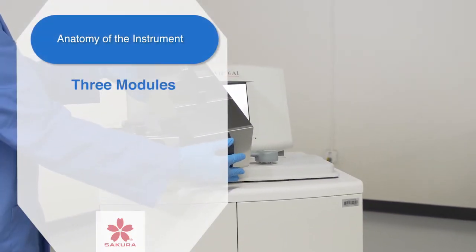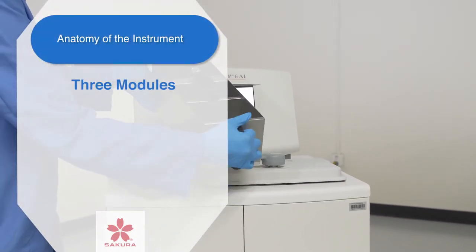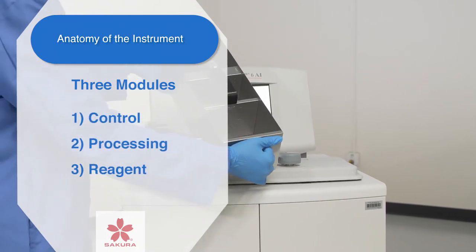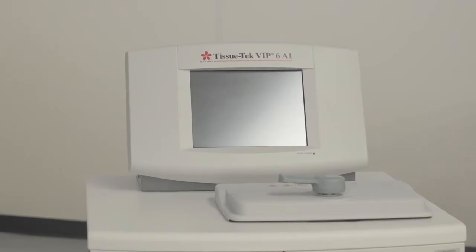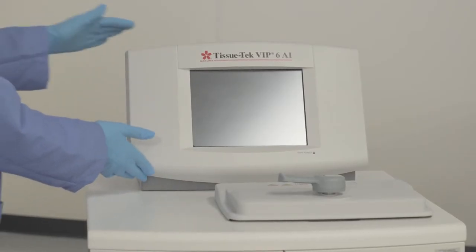The VIP 6AI consists of three modules: control, processing, and reagent. The control module provides user interface options. It receives and stores user data and is the brains of the unit.